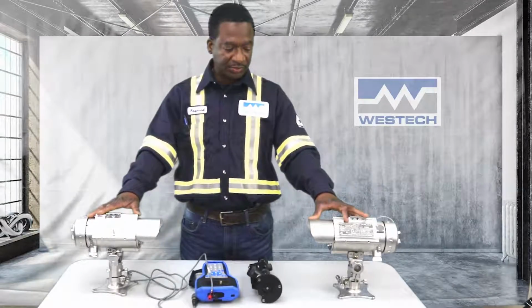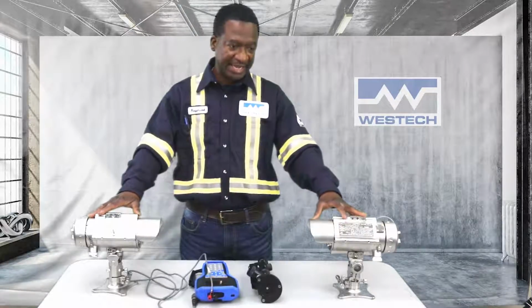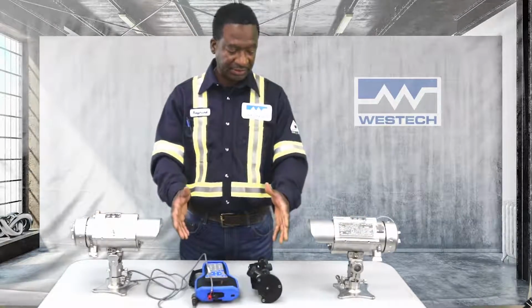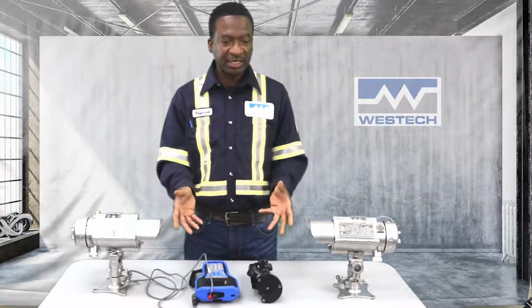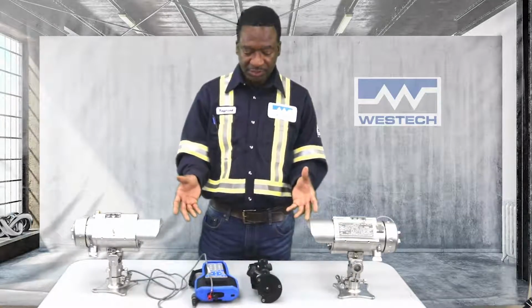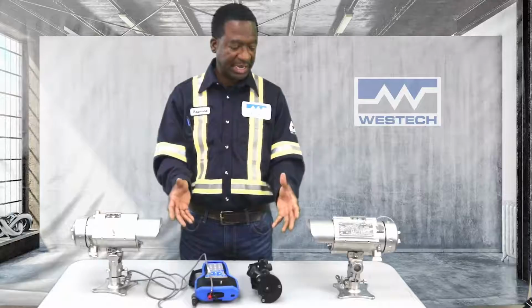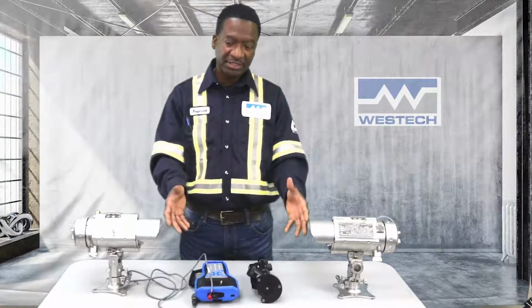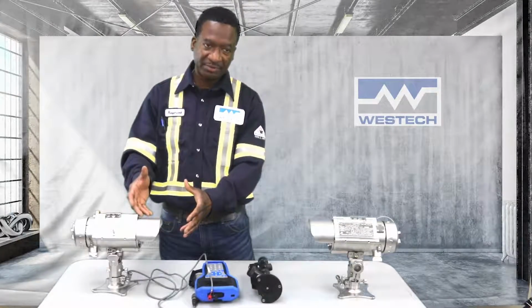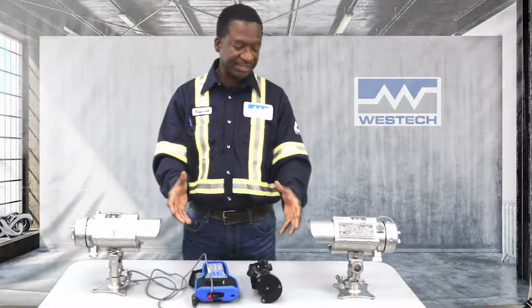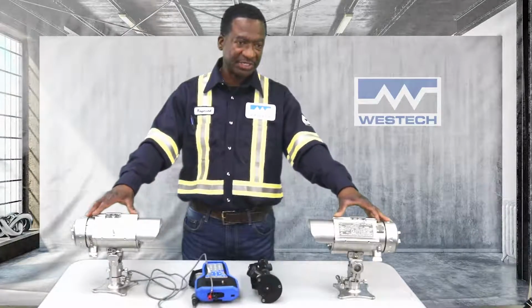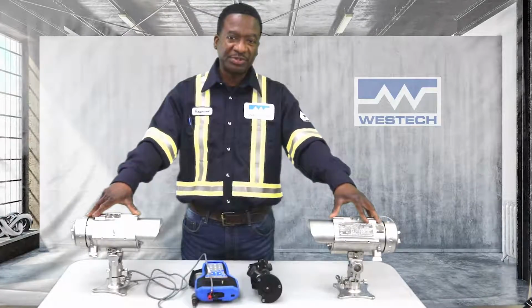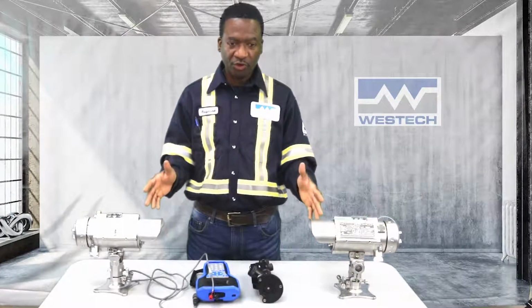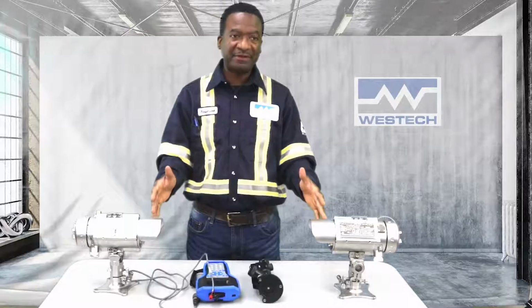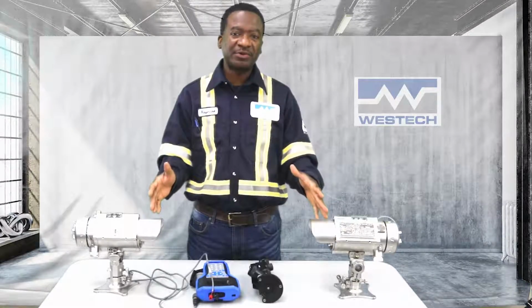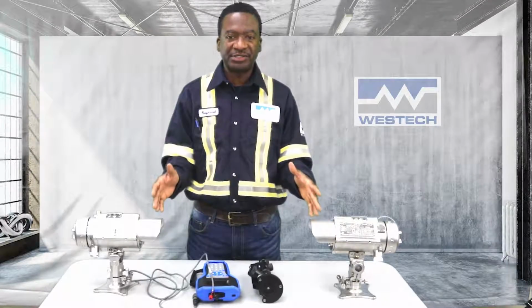It is important to note that if a gas cloud comes between the components, the gas cloud will absorb some of the transmitted energy from the transmitter, and the receiver picks that up, and there is a comparison between the transmitted beam and a reference beam. The ratio of the absorbed beam to the reference beam is a direct correlation of the gas concentration.